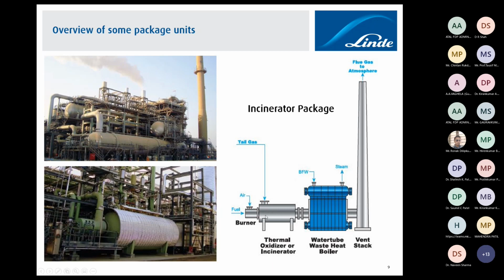Whenever you are making any destruction with a burner, a lot of flue gases will be generated, and you have achieved your target of destruction. But again, these have the value of high-temperature gases, so we cannot liberate them into the stack. So before we liberate them, typically in industries, we mount a waste heat recovery boiler. The waste heat recovery boiler basically recovers all this heat. Boiler feed water goes in and steam is produced at different levels, low pressure or medium pressure steam, and sometimes, depending on the flue gas availability, you can also produce high pressure steam. And once it is done, typically in the range of 150 to 250 degrees centigrade, it is safe to liberate into the stack.